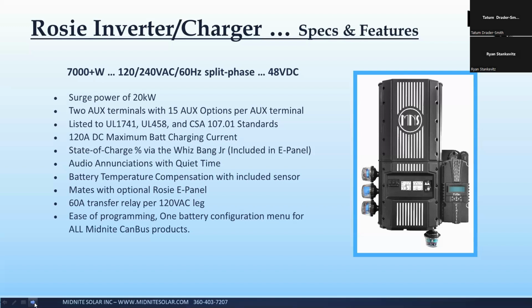And you will be able to disable parallel threshold as well if you want. One of the reasons for that really is if you've got one singular very large load. If that hits on a system where your parallel threshold is enabled and your followers are actually off, waiting to go to work, you lose a little bit of surge capability in that case, and it can be a little bit of a lag while those come on. I mean, it's milliseconds, but it's there, to like a motor load or something. So you can tune that out if the system is large enough and needs that.